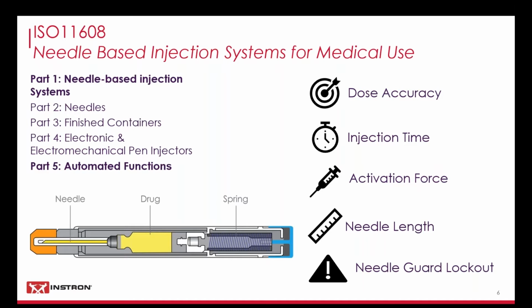The individual subsections refer to different types of injection systems or the testing of device subcomponents. When testing autoinjectors and pen injectors, the two most applicable subsections are Part 1 and Part 5. Part 1 is the most generic section and mainly focuses on the functionality of the device related to dose accuracy and reliability. Dose accuracy is one of, if not the most crucial parameter for a needle-based injection device.